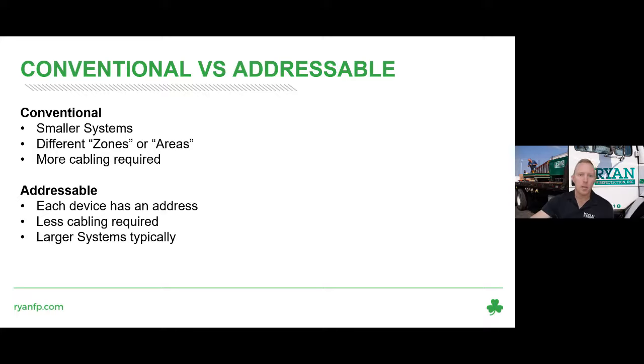Thanks, Adam. So like I mentioned before, we're going to talk about the difference between conventional and addressable systems. Conventional systems are typically smaller type systems, meaning fewer devices, smaller facilities, or maybe just a sprinkler system with no other alarm devices or equipment. In these systems, each device connected to the system doesn't have a specific address of its own, and it's not identifiable by the fire alarm panel, but rather each zone or area can be identified, such as a floor or an area of the building.